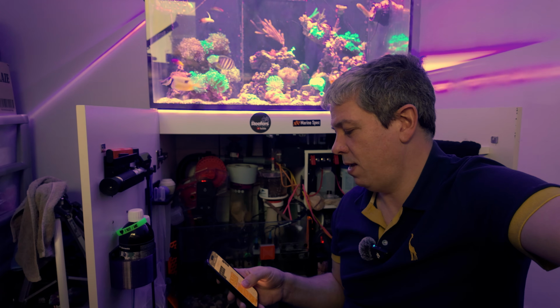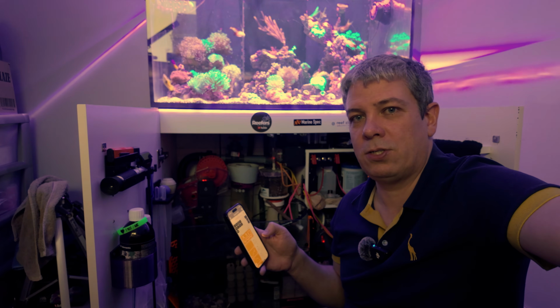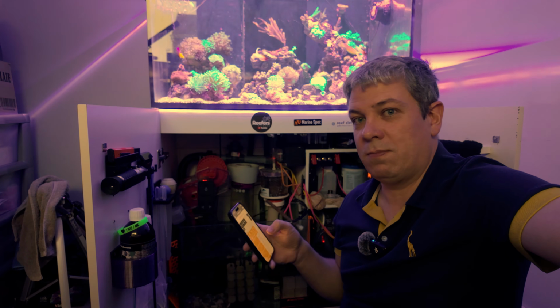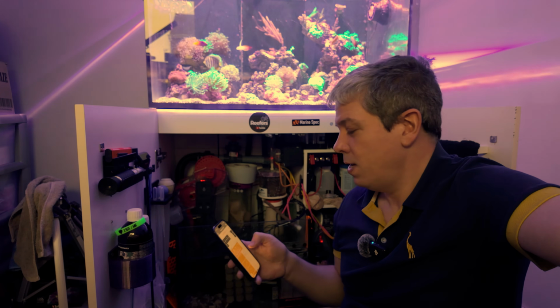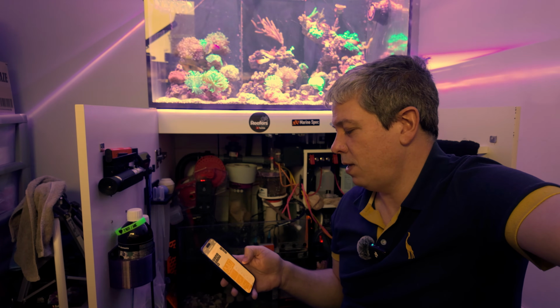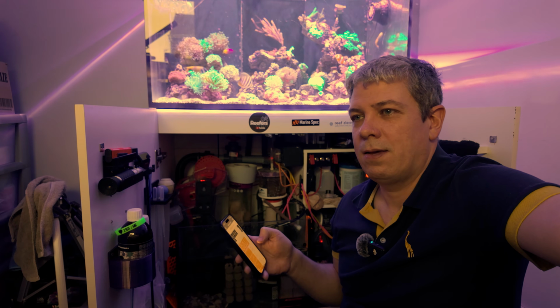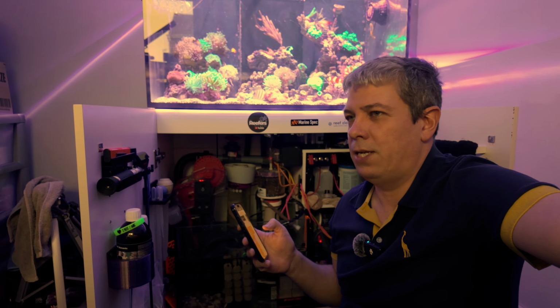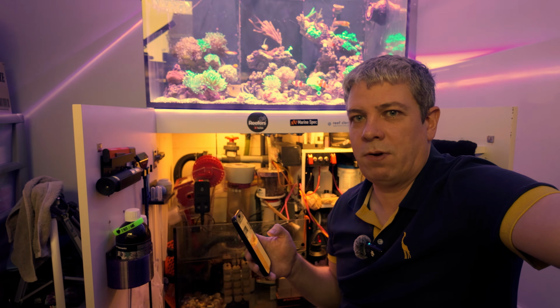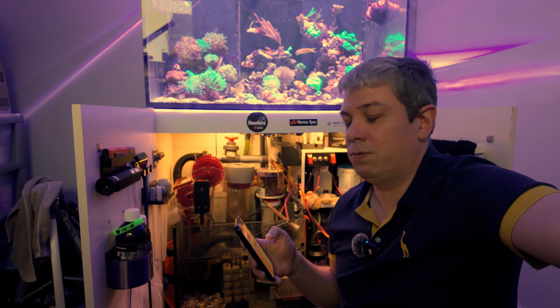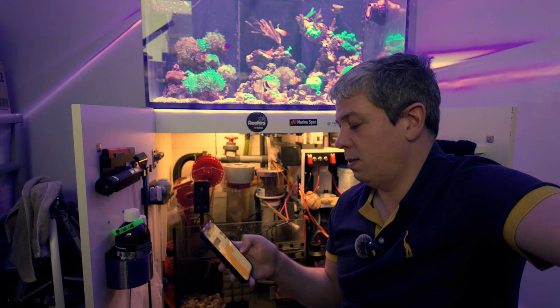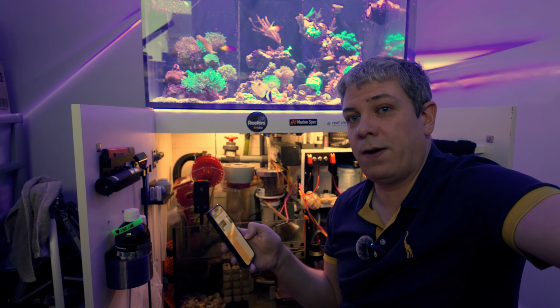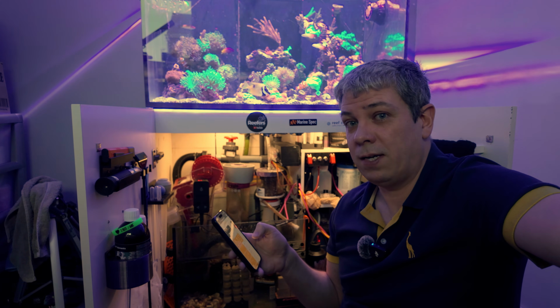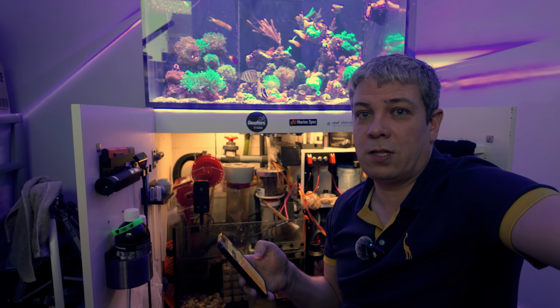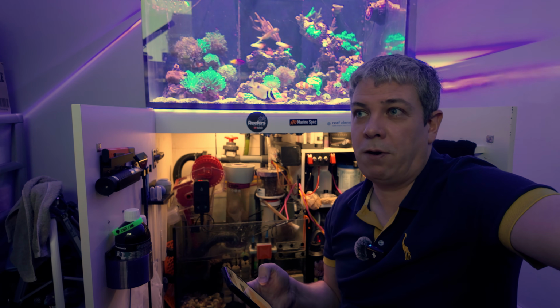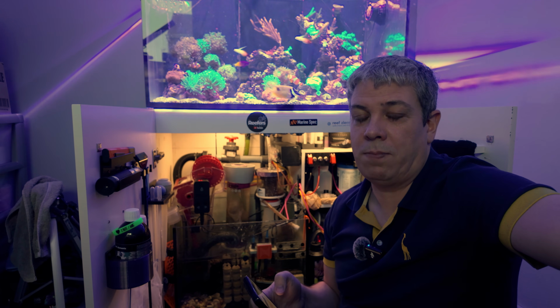So yeah, I mean it doesn't vary around much, and I just this minute performed another calibration on it. It had drifted out a little bit. It was at 33.9 parts per thousand, and it should have been at 35, so I checked with my refractometer and it was 35. So I've recalibrated it now and the probe is sat at 34.9. So still not perfect, but no worse than the genuine Apex probe and a hell of a lot cheaper.